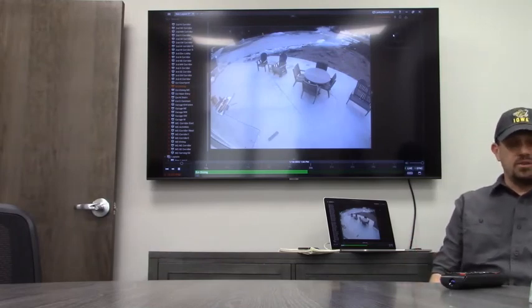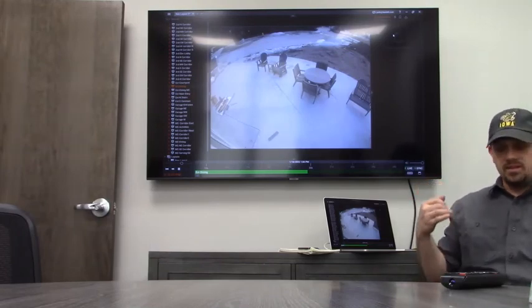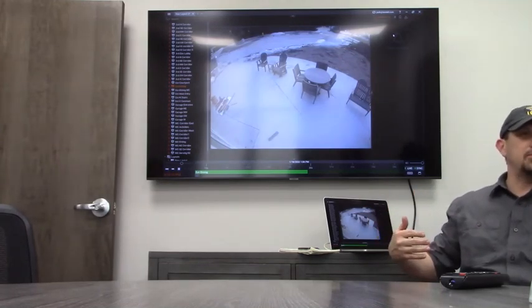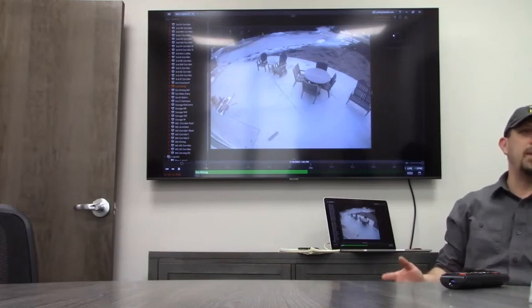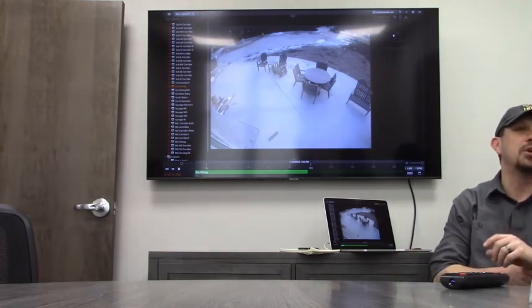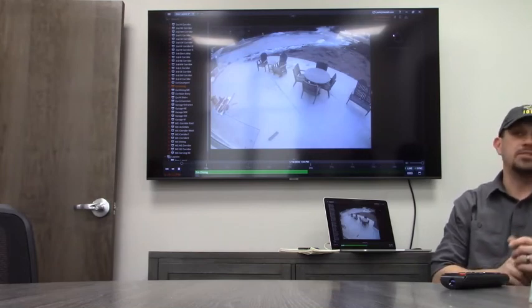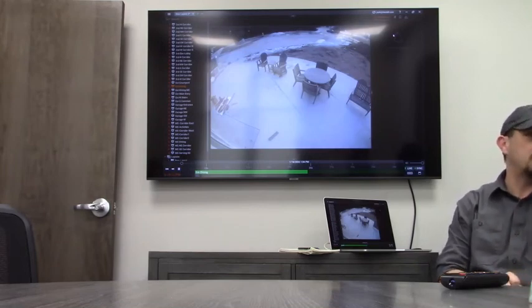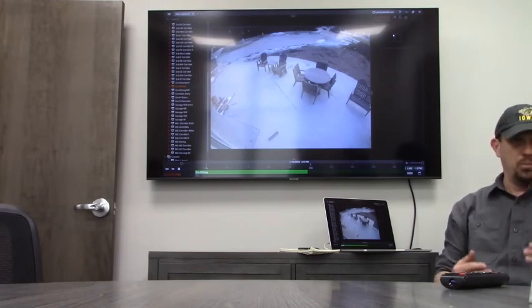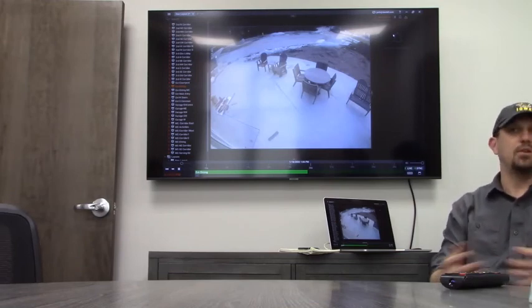The fire, so in that room above us, anything on the wall, on the hallway wall, is essentially fire alarm related. It all has its own battery backup. I don't worry about putting that on a generator. There's no reason to have that extra load on the generator because it all has its own battery backup system, as well as the card access system. So those two systems, I don't traditionally worry about putting them on the generator load because they're already battery backed up.